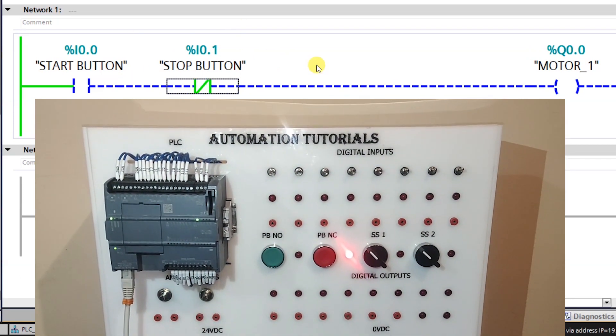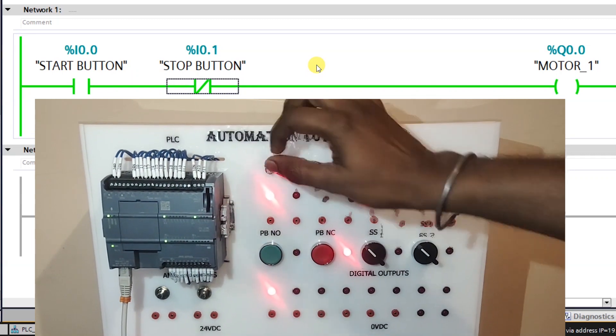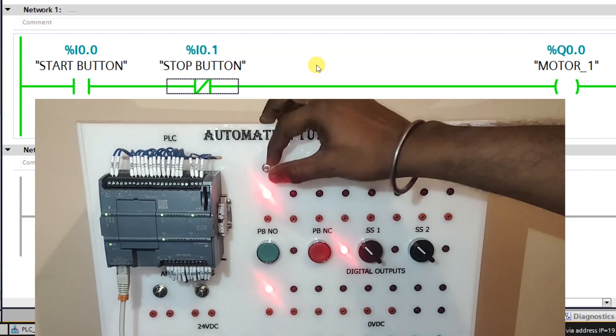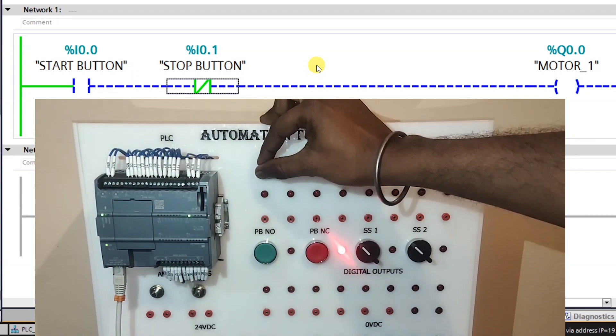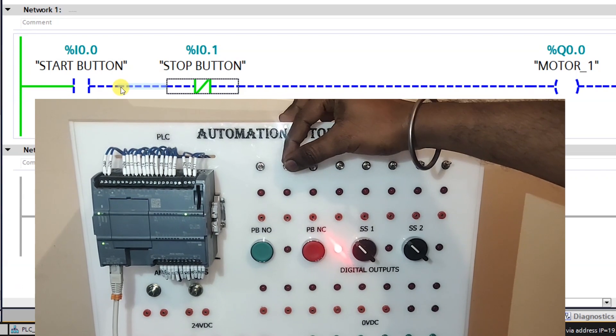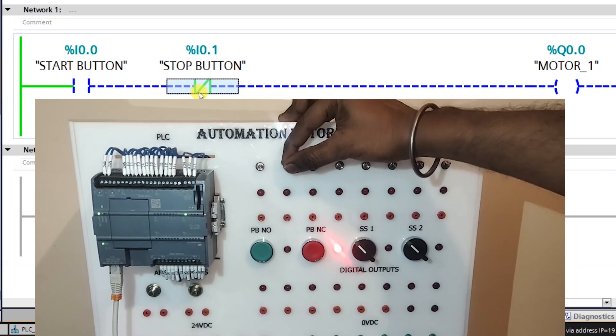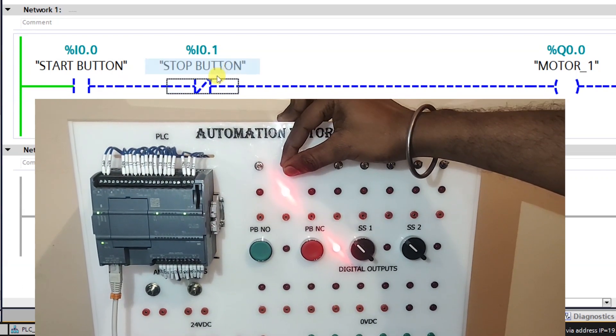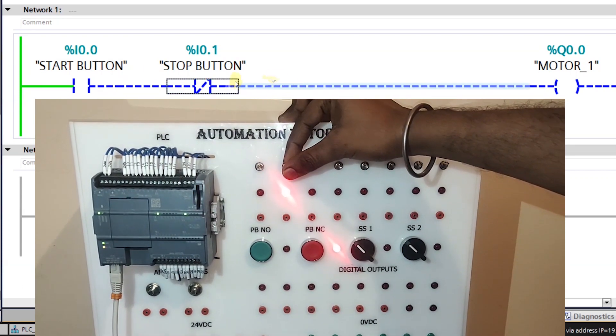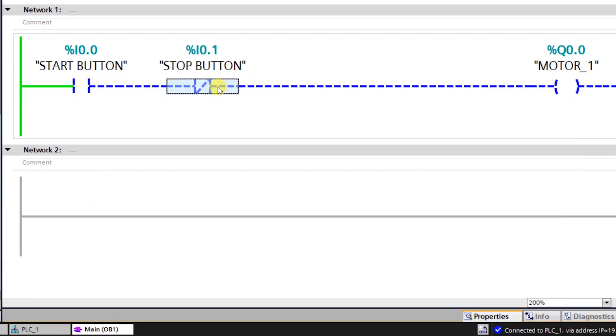Start monitoring by clicking the monitor icon. When input I0.0 is turned on, output Q0.0 turns on. If I0.1 is turned on, the output turns off because this NC contact blocks the signal. If I0.0 is turned off, the output also turns off. When I0.0 is on the signal is green; when I0.1 is on it goes off because it checks for 0 — that's the NO and NC logic.